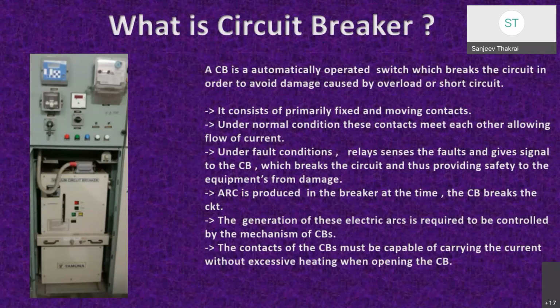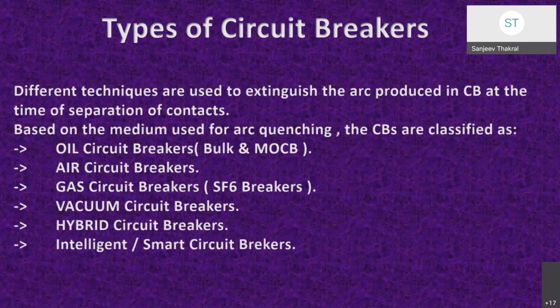The contacts of the circuit breaker must carry the load current without excessive heating. At the instant when the contacts begin to separate, the contact area decreases and the large current increases the current density, thus increasing the temperature, which results in heat produced in the medium sufficient to ionize. The generation of these electric arcs is required to be controlled by the mechanism of circuit breakers in order to avoid damage to the circuit breakers themselves.